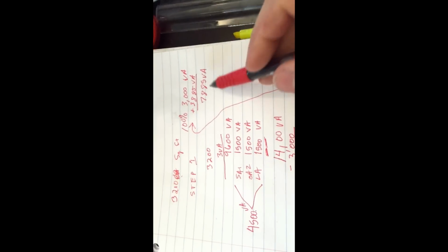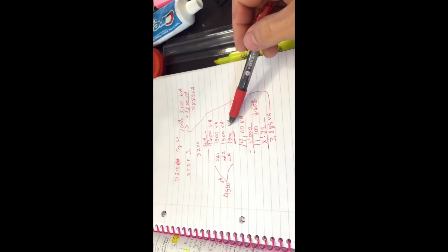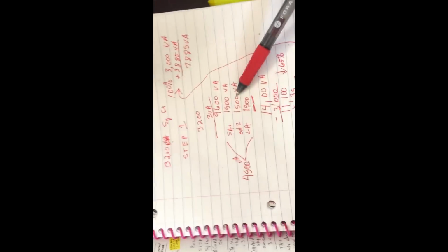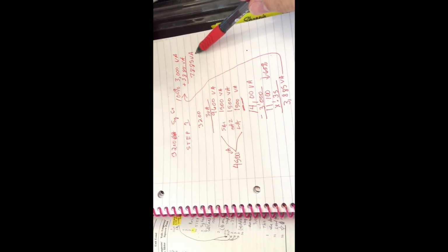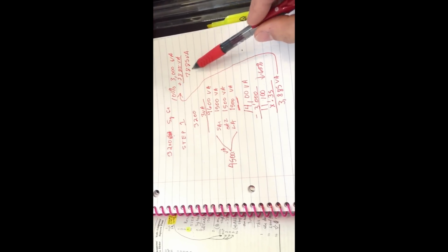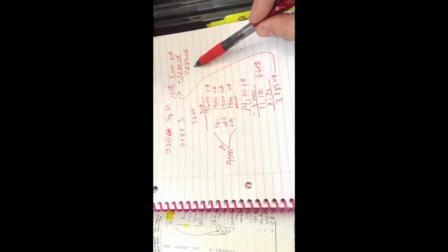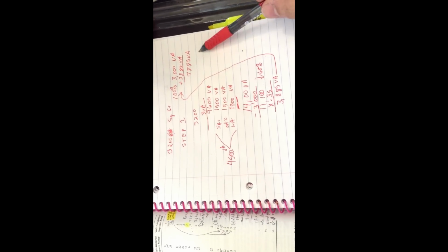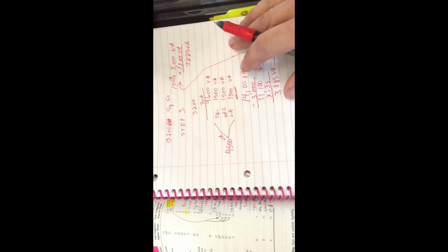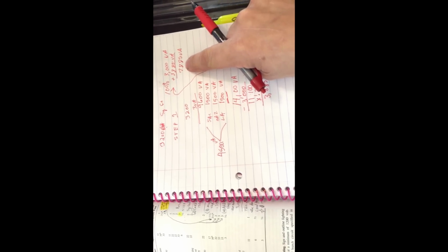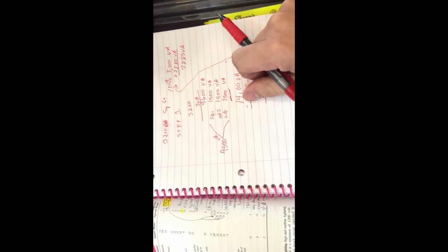Now, what do I do with this number? All of these numbers, first and foremost, are service calculations, meant to be used to size the feeder on the outside of the building. So the 7,885 is not a branch circuit calculation. It's not something I divide by 120 volts to figure out how many circuits I need. This is just the amount that goes along with the range calculated demand load, and the dryer values in demand loads, a minimum of 5,000 watts or nameplate, whichever is larger in the case of dryers. For the first 1 through 4 there's no derate, so it'd usually be 100% of the dryer, at a minimum of 5,000 VA. All of those items are similar to this number, and we add them all together to calculate the service requirements for the feeders on the outside of the building.